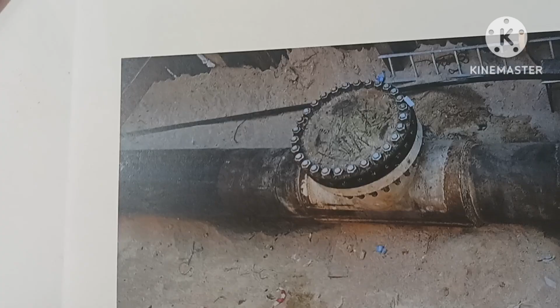That is the basic important point. When you go for selection of the location for hot tapping, it is mandatory to check internal corrosion, thickness, availability, defects on the pipe wall, and the outside wall. These are the important points, and checking must be done before the selection of the hot tap location.